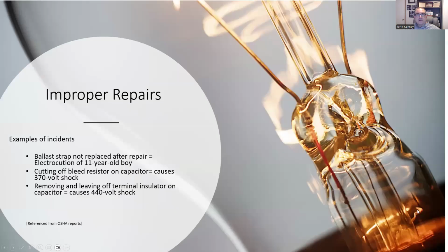Defective equipment or tools. One thing we have to remember is improper repairs. Examples of incidents: a ballast strap not replaced after repair, electrocution of an 11-year-old boy. These are examples of what we've heard out there. Cutting off a bleed resistor on capacitor causes a 370-volt shock. Removing and leaving off a terminal insulator on a capacitor causes a 440-volt shock. These are all from OSHA incidents that happened on job sites. Now, that doesn't mean this will affect you up on the roof, but the same thing has to be taken in context with the different types of equipment you use. And also, if you do plug into building power, you need to be aware of what you're plugging into.